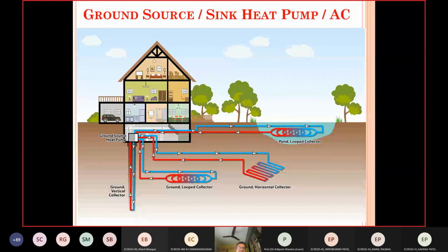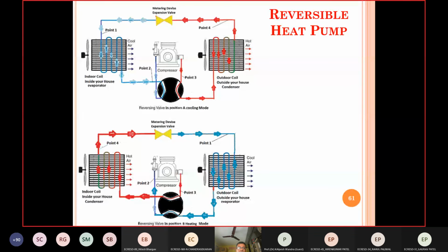In summer, the condensing unit of your air conditioning system will have to reject heat at a much higher temperature, so your COP or EER will be very low in harsh conditions. But if you are rejecting heat a bit deep in the ground, then your heat pump or air conditioner will have a higher energy efficiency.